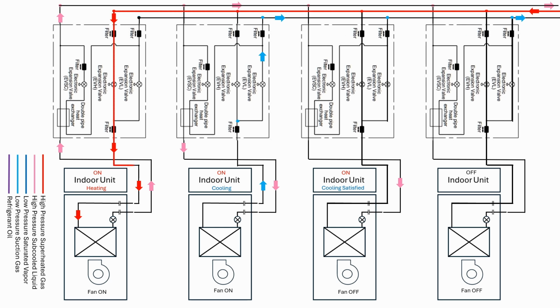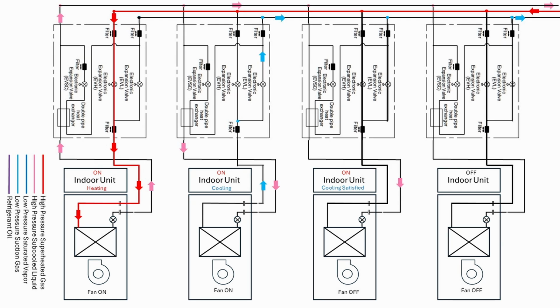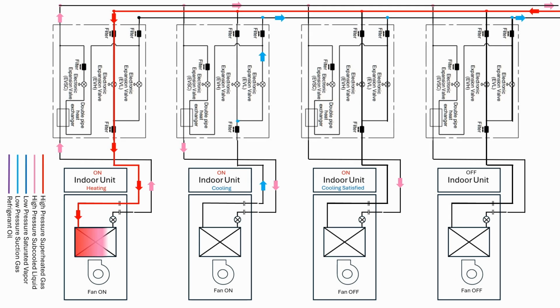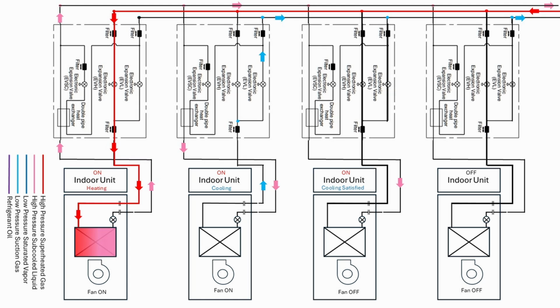The high-pressure vapor will be routed into the branch selector and then travel through an expansion valve which is pulsed wide open and not metering. It'll then be routed into the indoor coil. As the high-pressure vapor travels through the indoor coil, the refrigerant is being subcooled into a liquid and giving off heat to the space.